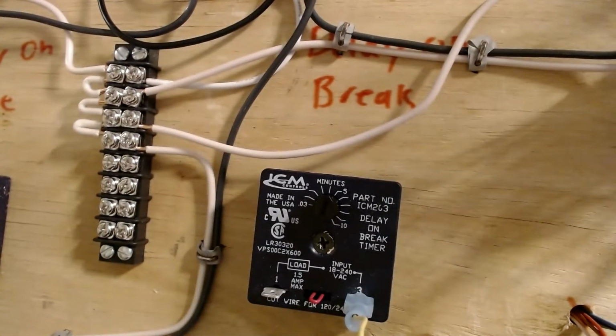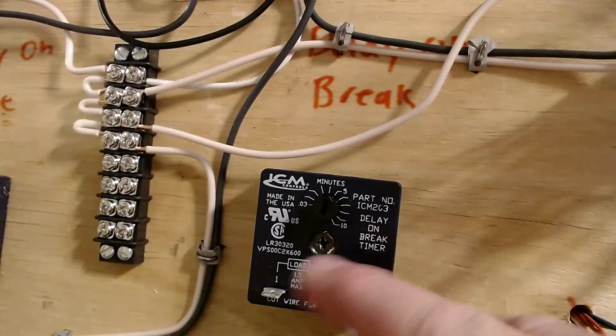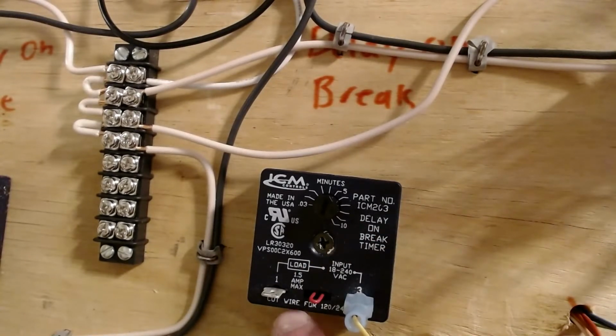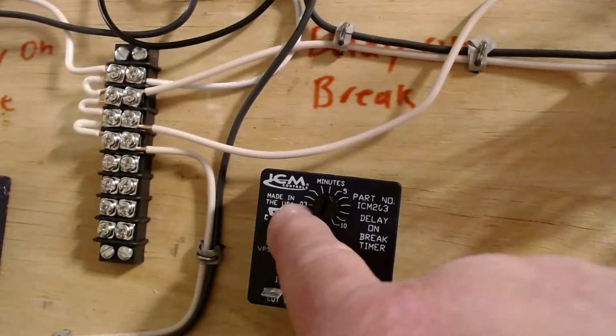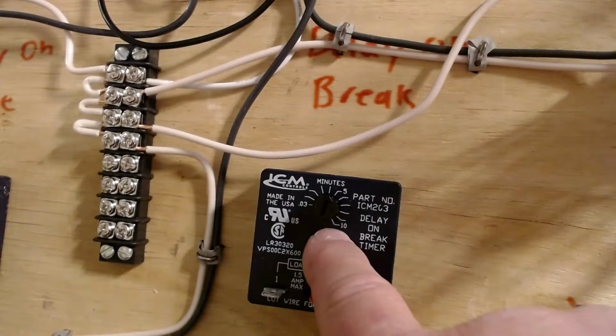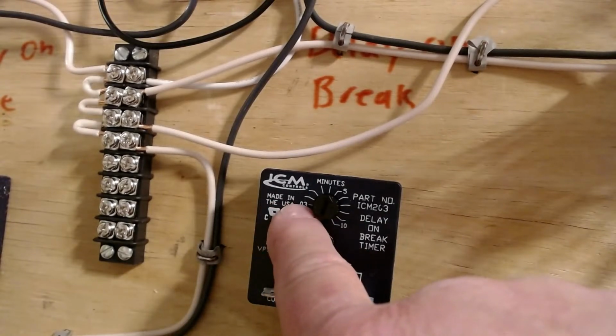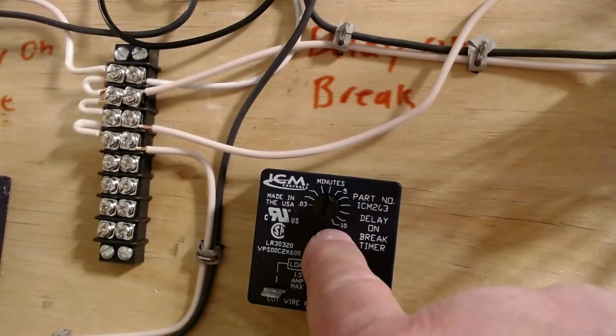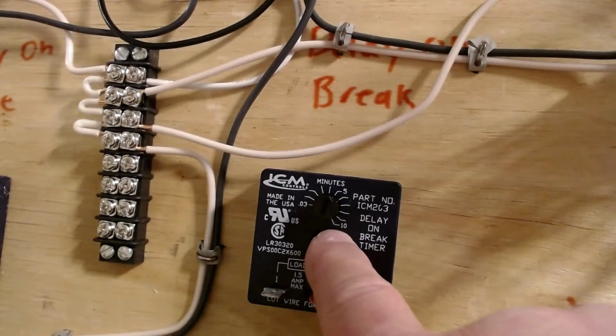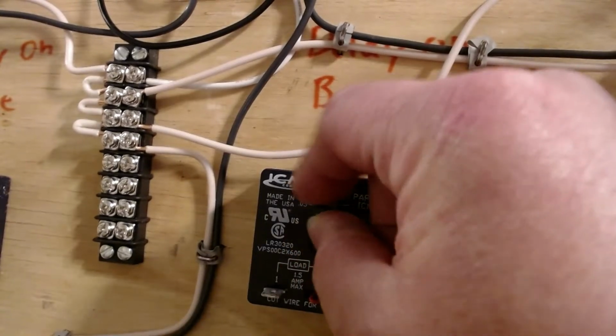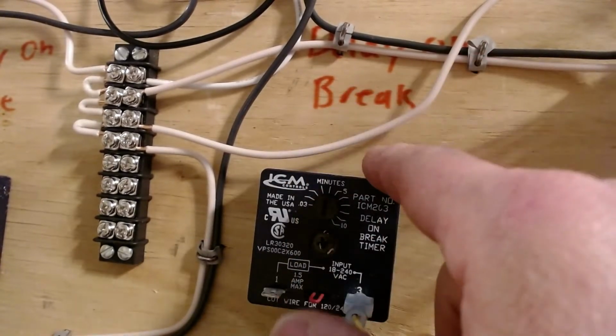There we go. So as you can see, your break and make timer have these same settings here. And if you look on the bottom, it says cut for 120 volt. That's the same on the bottom of the other one. You cut this wire if you're making a 120 volt. 30 seconds all the way up to 10 minutes. So you can go 30 seconds or up to 10 minutes on a timer. So you can set this wherever you want and it will delay on that break.